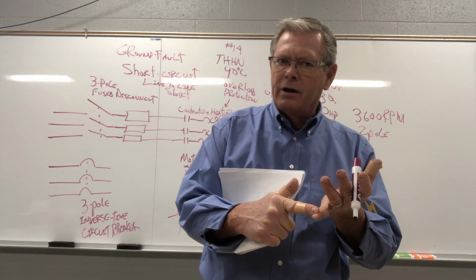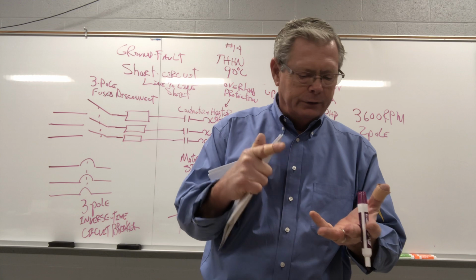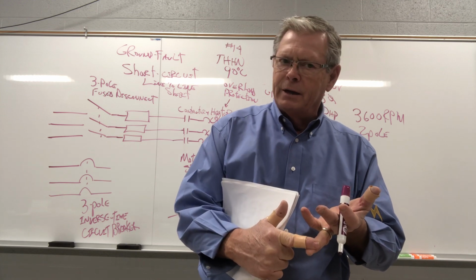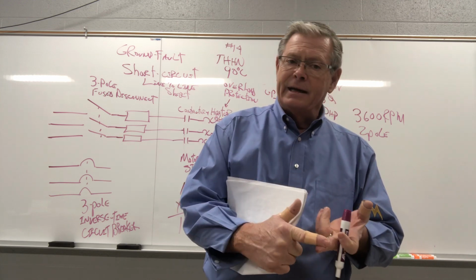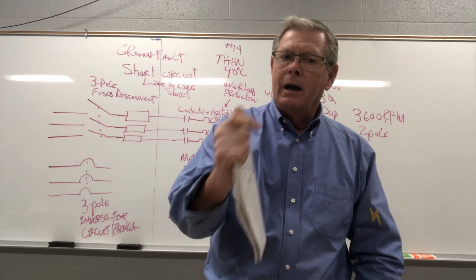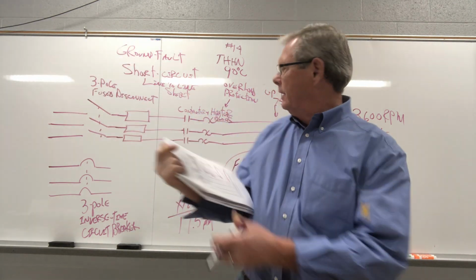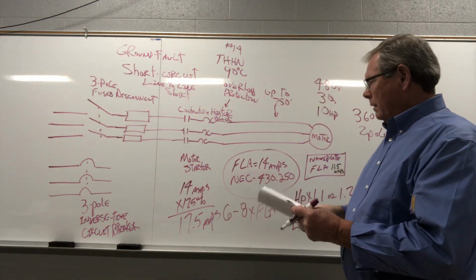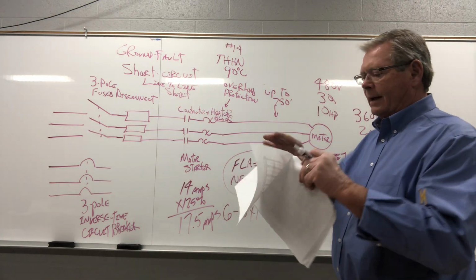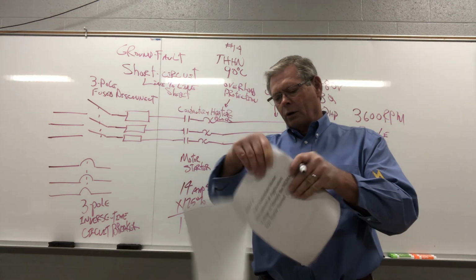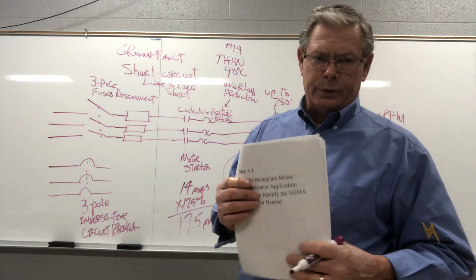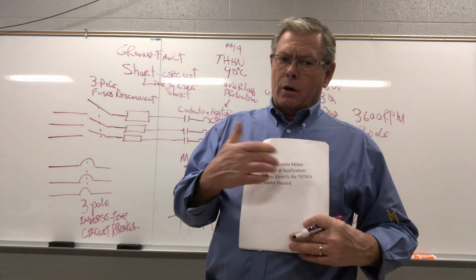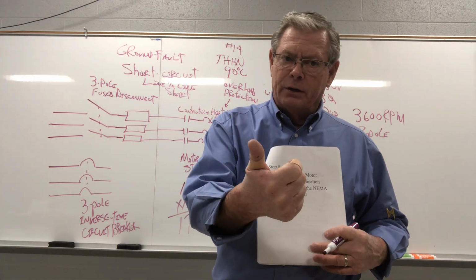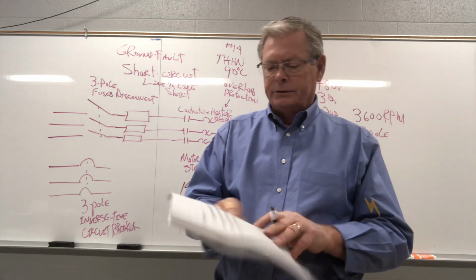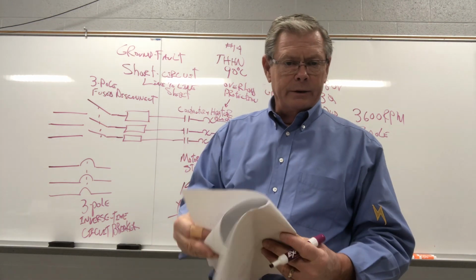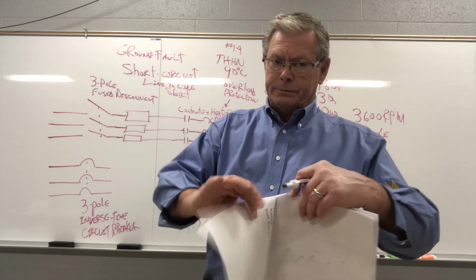14 gauge wire never on anything bigger than a 15 amp breaker or fuse. 12 gauge wire never on anything bigger than a 20. And a 10 gauge never on anything bigger than a 30, unless it's a motor circuit, okay? So we're gonna pull 14 gauge wire. Now, we are going to select the starter size we need. Now, all we need is the application voltage and the horsepower. So it's a 480 volt motor and it's 10 horse motor.